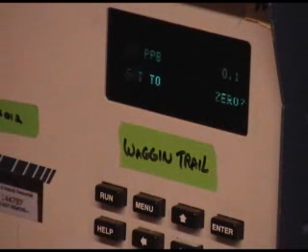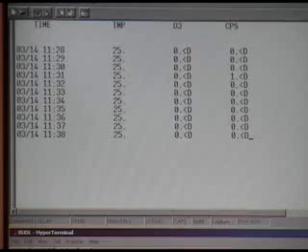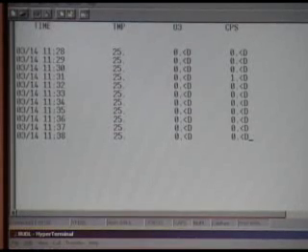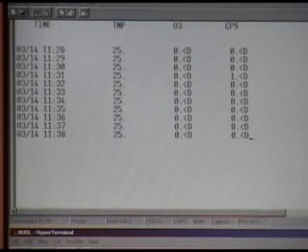Now we're going to see how we like it. We're going to let it run for a while. See if it looks a little bit better than what we started out with. Hopefully not worse. Otherwise we'll just hit set to zero again. So far our zero calibration is looking really good, looking really tight. I think we're going to start taking readings at about 11:40. Take 5 consecutive readings. And then we'll be moving on to our level 4, 225 parts per billion.